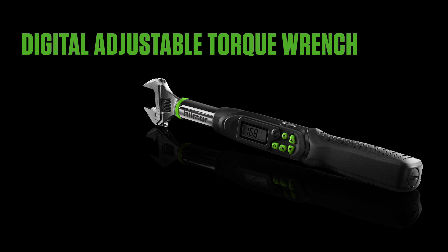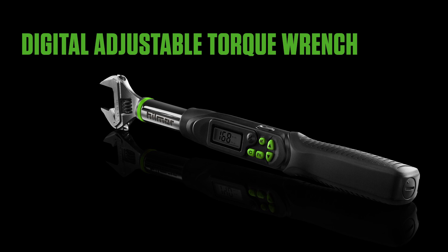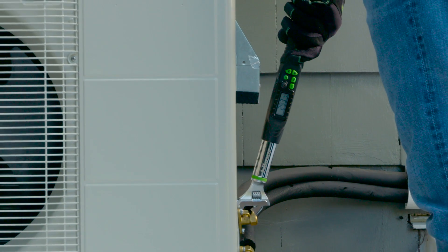When you're tightening flare nuts on mini-splits, achieving the perfect torque is critical for preventing refrigerant leaks. Hilmor's digital adjustable torque wrench makes setting torque as easy as a push of a button. Start by confirming the torque specified by the mini-split unit manufacturer. In this case, it's 32 foot-pounds.